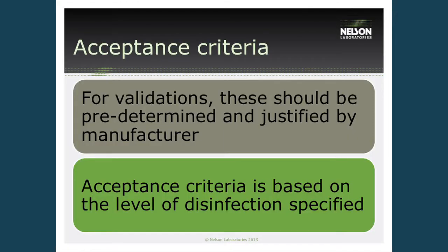So for disinfection validations, again, they should be predetermined and justified by the manufacturer. This is a little simpler. There's a lot more information out there for disinfection validations. There's an FDA Class 2 guidance document that specifies the organisms and the log reduction criteria, and I can give that information to anybody who's interested. Also, ST58 from AAMI has more specific guidance on the acceptance criteria for disinfection validations.